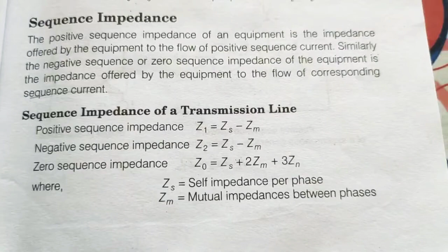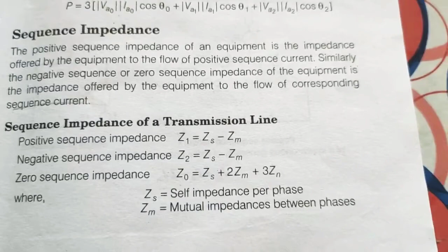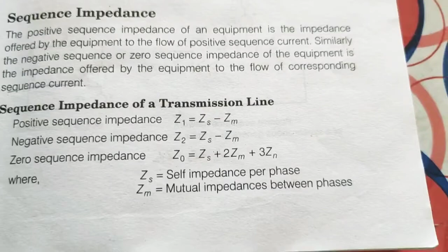Sequence impedance of a transmission line: positive sequence impedance Z1 is equal to Zs minus Zm. Negative sequence impedance Z2 is equal to Zs minus Zm. Zero sequence impedance Z0 is equal to Zs plus 2Zm plus 3Zn, where Zs is the self impedance per phase and Zm is the mutual impedance between two phases.